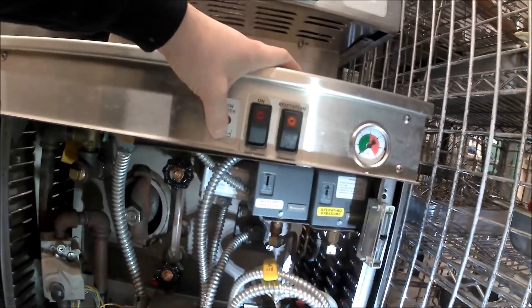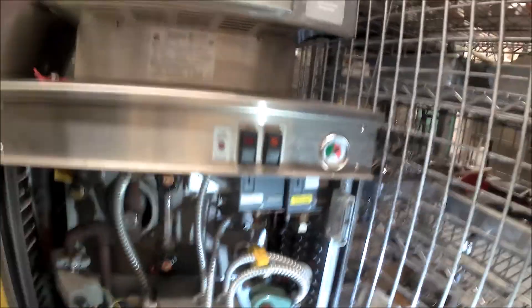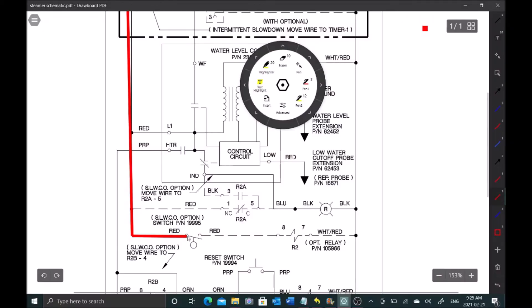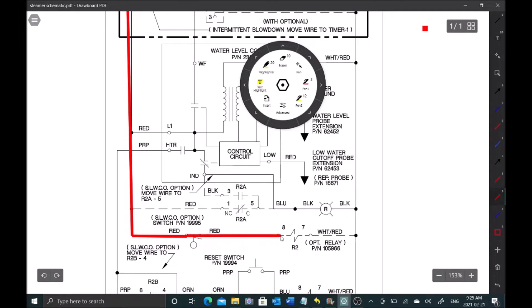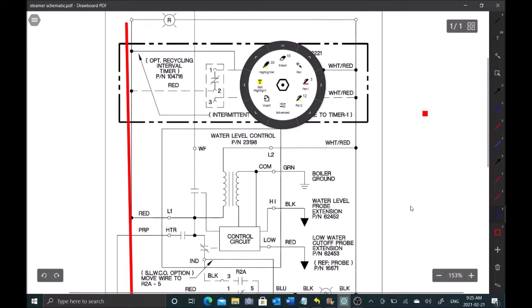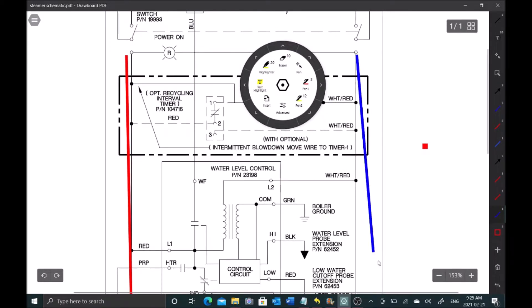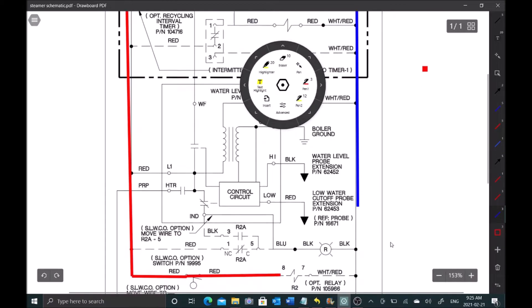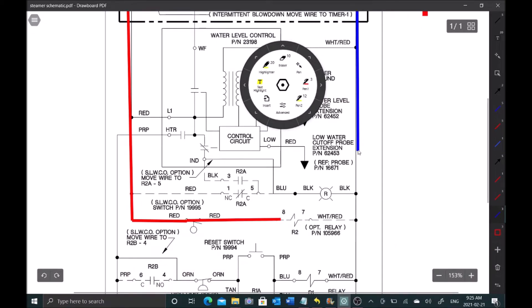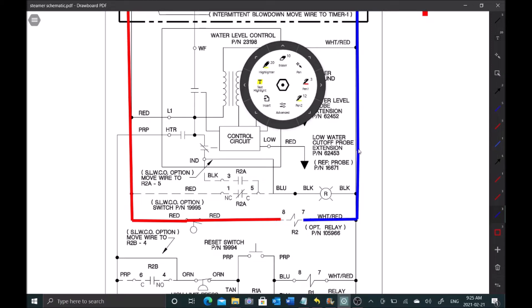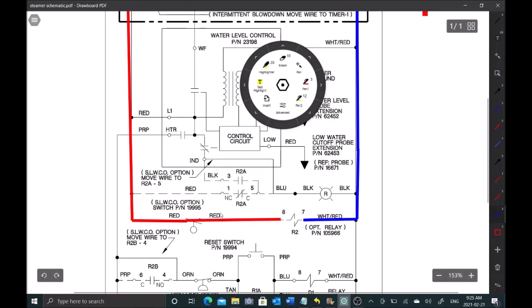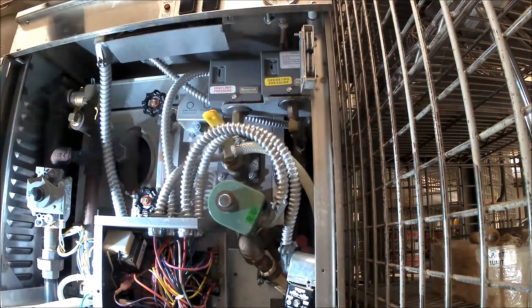What I've done here is I've jumpered out this switch, so I disconnected and connected the wire from the low water cutoff inlet to this relay coil. What that's going to do is complete my circuit to my relay coil. The reason I'm doing that is I want to make sure there's no other components that have failed. I got to order this part, this low water cutoff. I want to make sure my module, my gas valve, everything else is working, so I'm jumping this out temporarily just for troubleshooting.